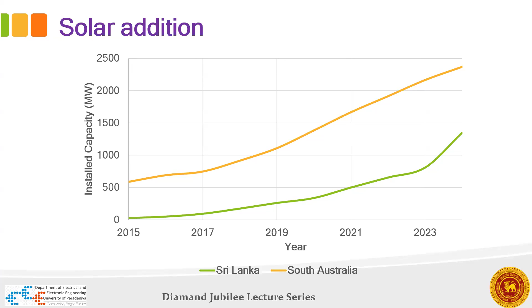In terms of blackouts, everybody knows about the 9th February blackout. We were told there was a grid failure on part of the network, and that grid failure created a huge voltage dip, which took off around 300 megawatts of rooftop solar from the system. This created an immediate deficit in the demand-supply balance, and that eventually led to a blackout.